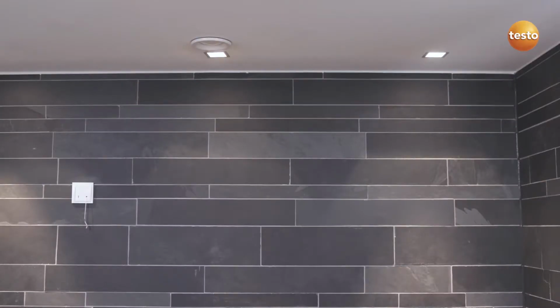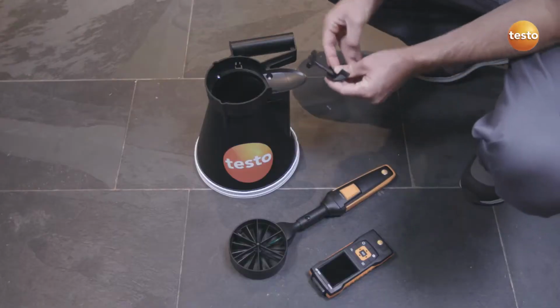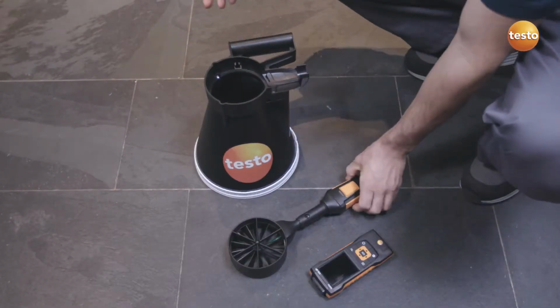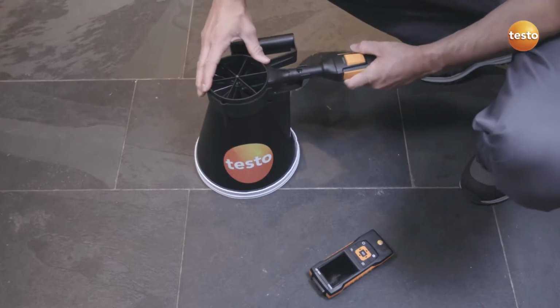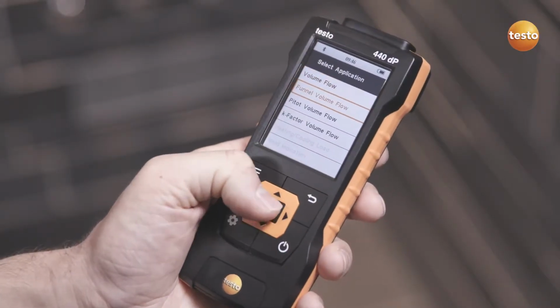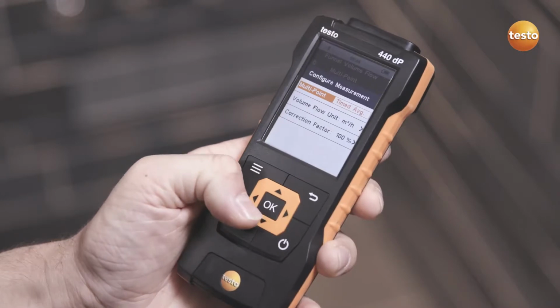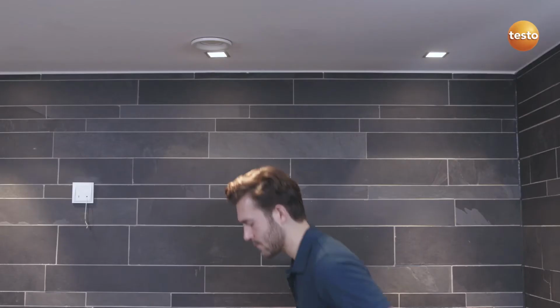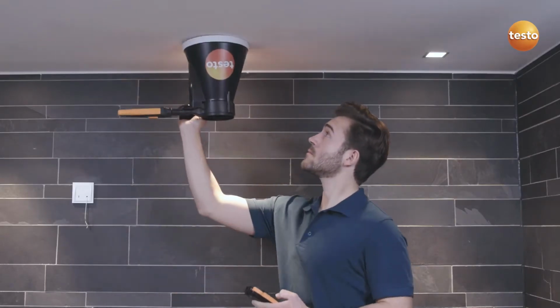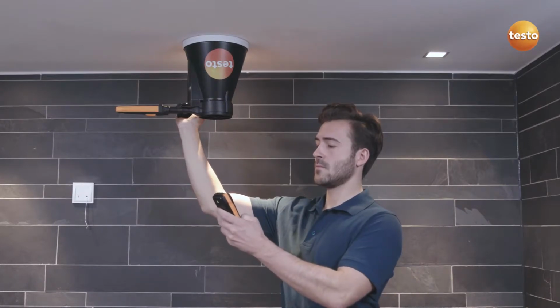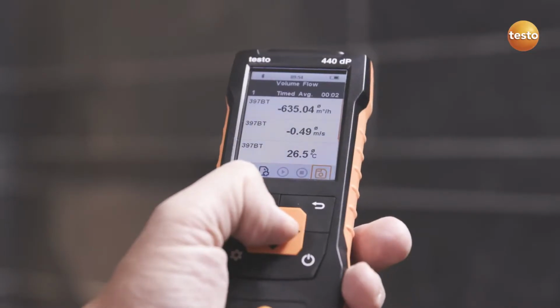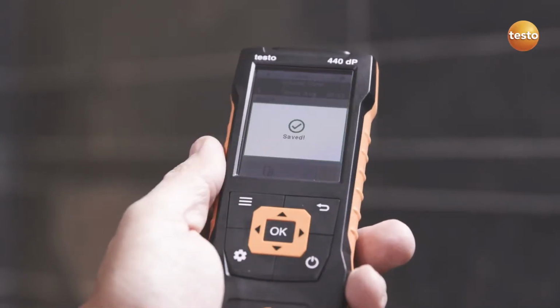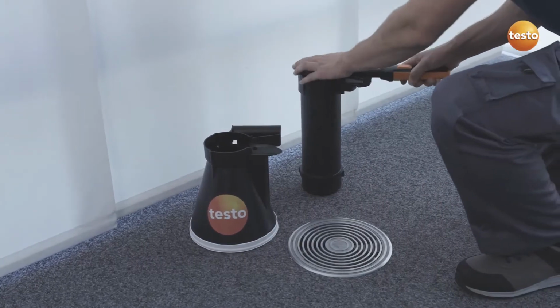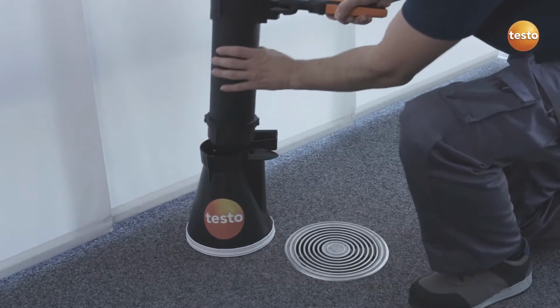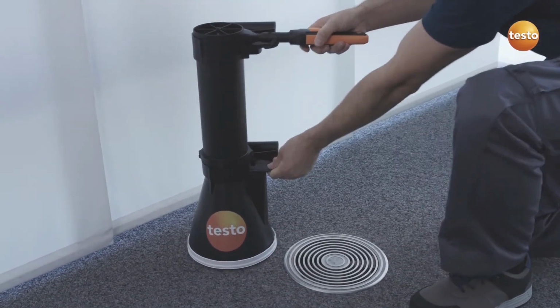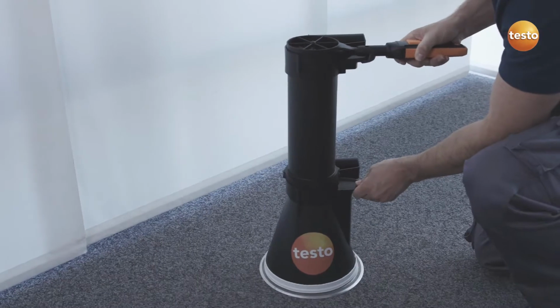For exhaust air measurements at outlets, the Testo 440 with the 100mm vane probe and Testo vent funnel is recommended. In the special measurement for calculating volume flow, the correct funnel factor is automatically selected corresponding to the connected probe. This makes the measurement even easier. And with the combination of the 100mm vane, the funnel, and the flow straightener, you can obtain exact results even in turbulent flows.